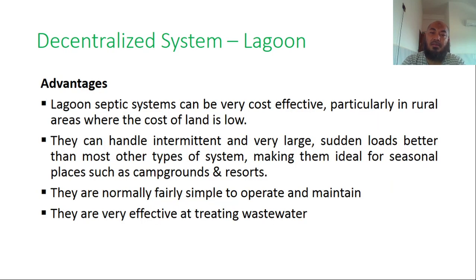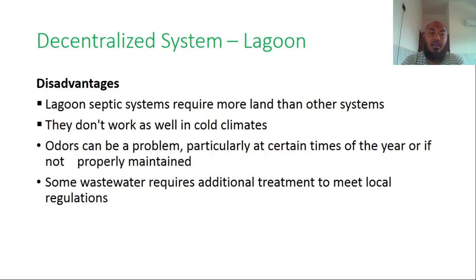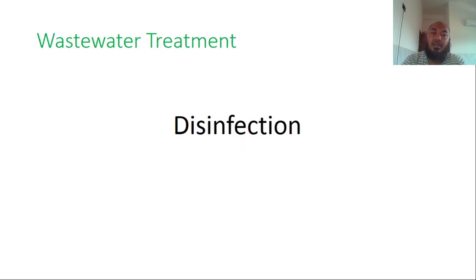Advantages of lagoon septic systems: they can be very cost-effective, particularly in rural areas where land cost is low. They can handle intermittent and very large sudden loads better than most other system types, making them ideal for seasonal places such as campgrounds or resorts. They are normally fairly simple to operate and maintain, and are very effective at treating wastewater. Disadvantages: lagoon systems require more land than other systems, they don't work as well in cold climates, odor can be a problem at certain times of the year or if not properly maintained, and some wastewater may require additional treatment to meet local regulations.